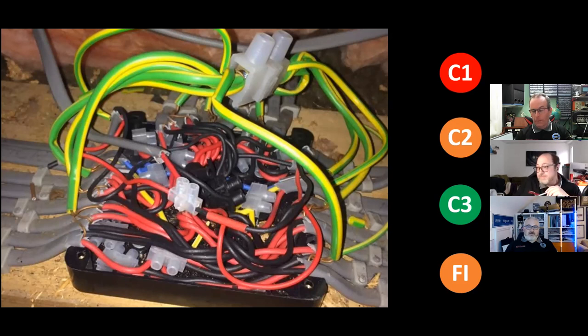For me, I would actually see one of those, and the reason being, it's in a loft. There are live parts that a smaller person could potentially go in and touch, and they could come loose. That's going to make you need to remove that danger, ideally. So what are you going to do? Just turn it off? I would say that needs to stay off until that gets fixed. And I guarantee the homeowner would probably say, can you please fix it? And you'd be like, great, 5-6 hours in a loft for my sins.